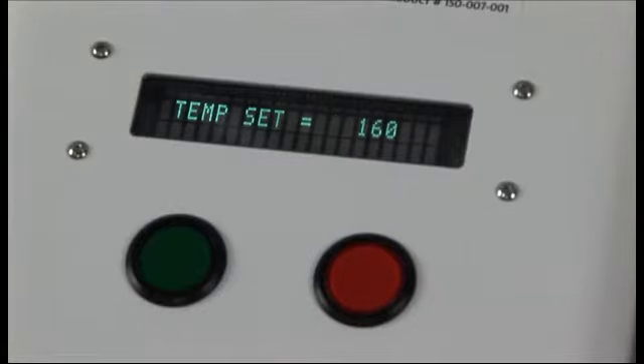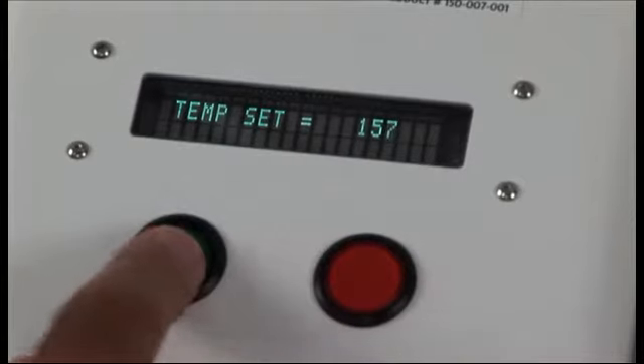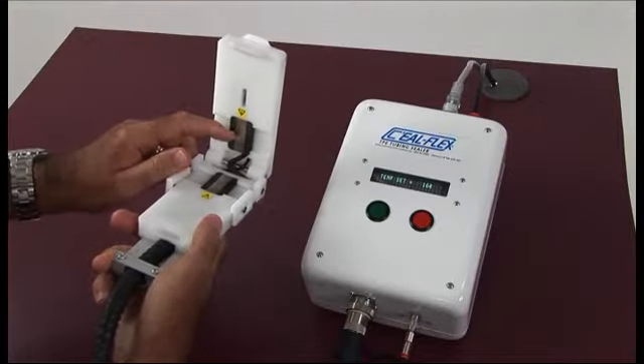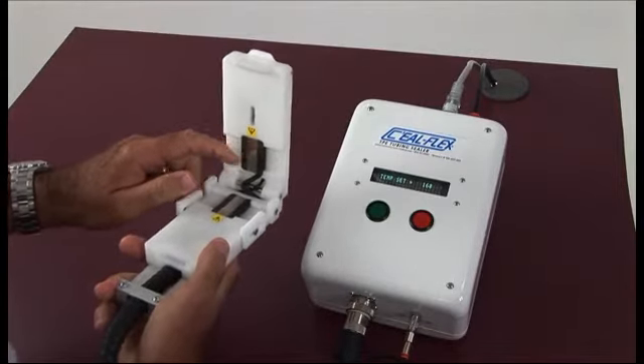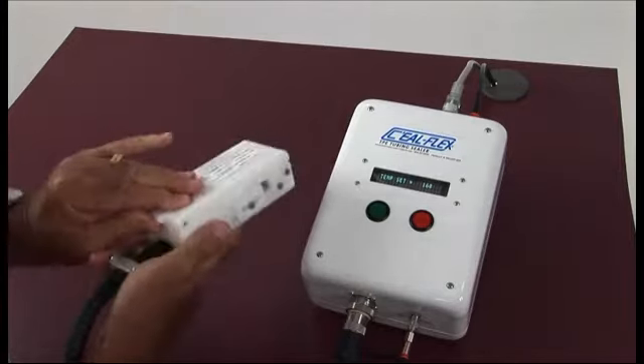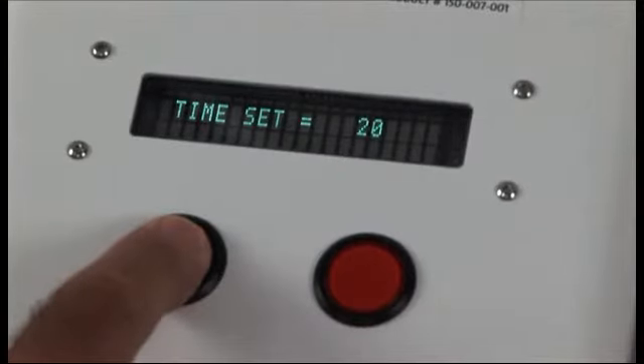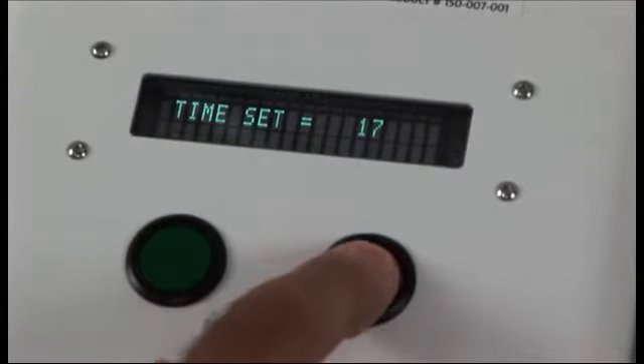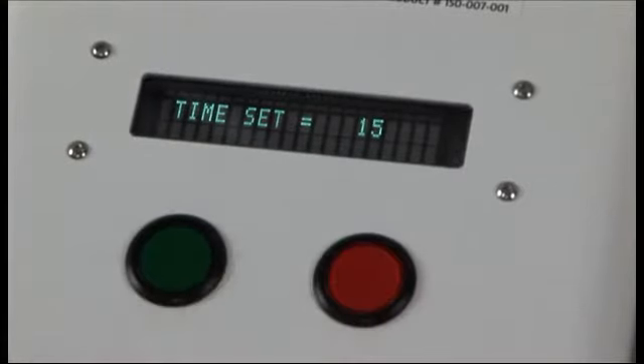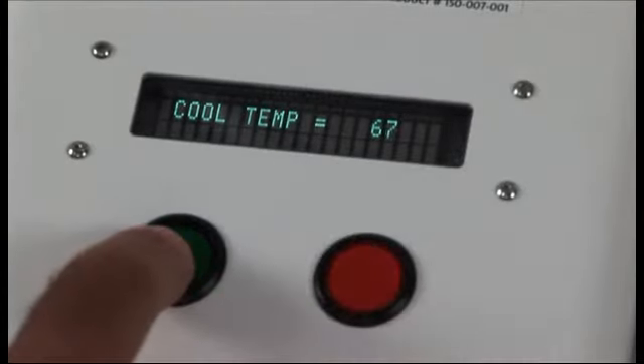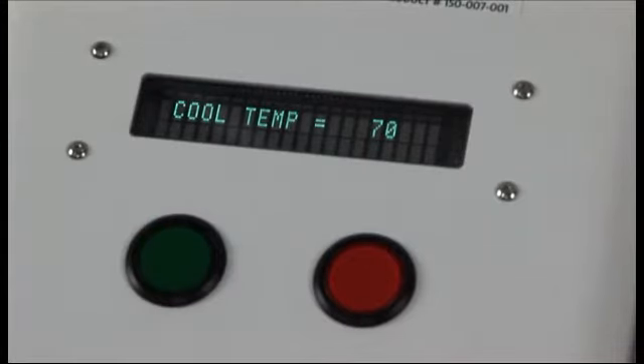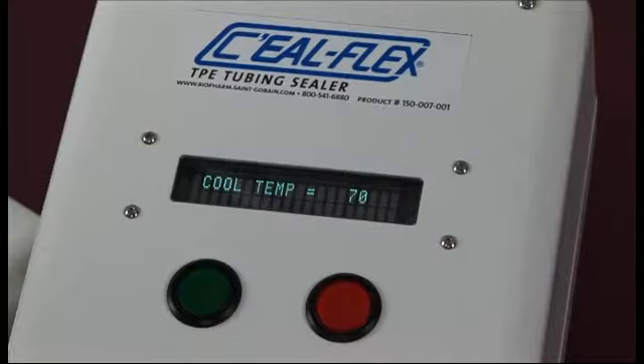First, the temperature setting. Optimum for C-Flex is 160 degrees centigrade on the upper and lower heads. The time set once the head is closed: we want it to stay closed at the temperature level for 17 seconds. We set a cool down temperature of 70 degrees. The head will release the lock when it reaches that temperature, and you can open the head. Then you also have a cool time maximum set at 33 seconds before the head will open.